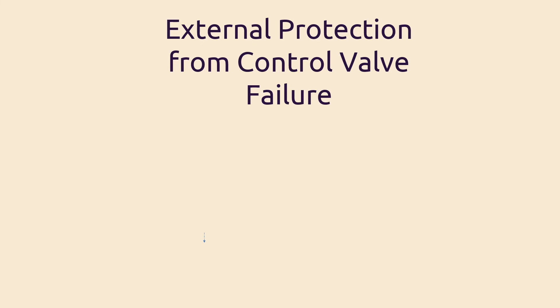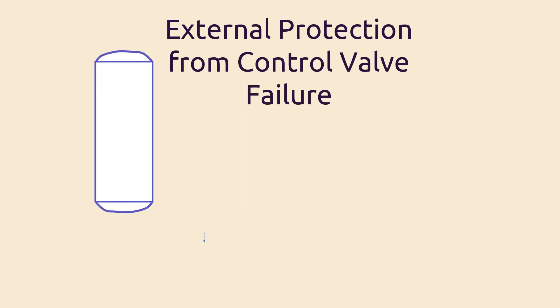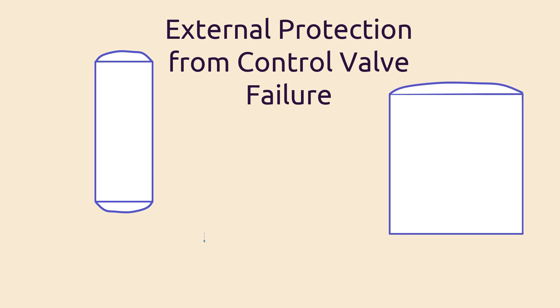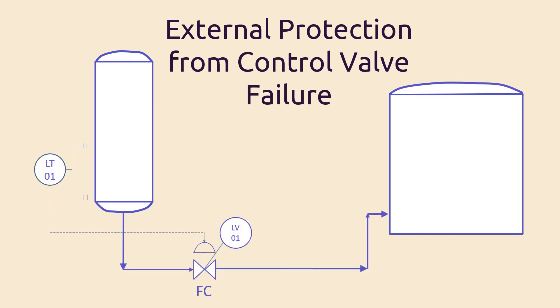So we have addressed the valve fail action, which shall reduce the risks if the air supply is cut. But what if the valve experiences mechanical failure? In this case, we would need another protection to protect our equipment. Suppose we have a vessel operating at 3 barg. The bottom liquid from the vessel is then transferred to a tank operating at atmospheric pressure. The pressure is dropped through a level control valve LV01.